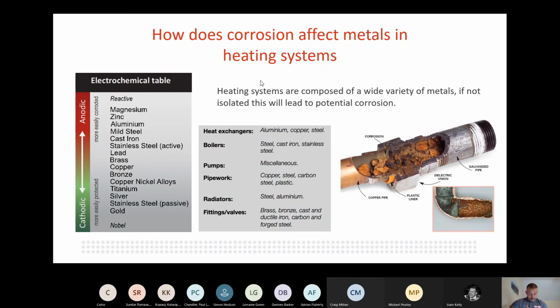As you can see here, different metals in contact in the heating system create a corrosion cell, as Craig said. Corrosion will take place. According to the table on the left, titled electrochemical table, one metal will corrode preferentially to another, and it's determined by the metal's position on this table. The greater the distance between the two metals, the greater the driving force of corrosion between the two. Depending on the component that it's made of, that's what will be left in the system.